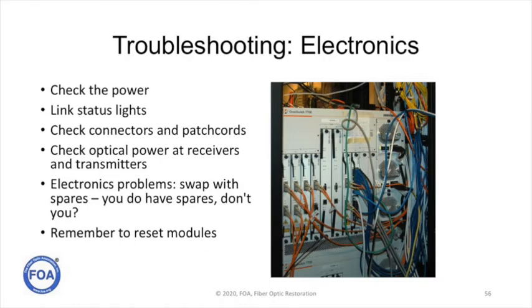When you start troubleshooting electronics, you start with the first thing you do with anything electrical — you check the power. You see if it's already kicked into backup power, which might have glitched the modules. You check link status lights and look for greens. When you start checking the fiber, check the connectors first to make sure they're clean and good, and patch cords to ensure nobody has damaged them. We can check the optical power at the receivers and transmitters to see if they're within spec. You're going to have to swap modules that are bad for spares, which should have been part of your planning process. Remember after you swap them that you often have to reset them before they will operate.